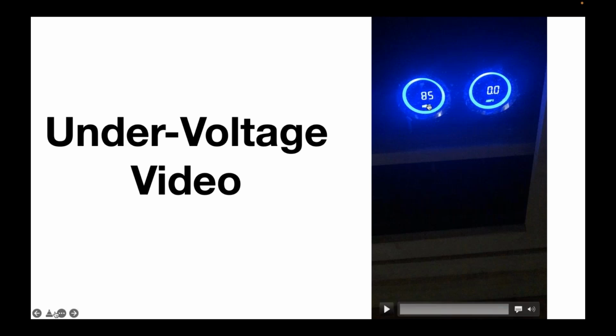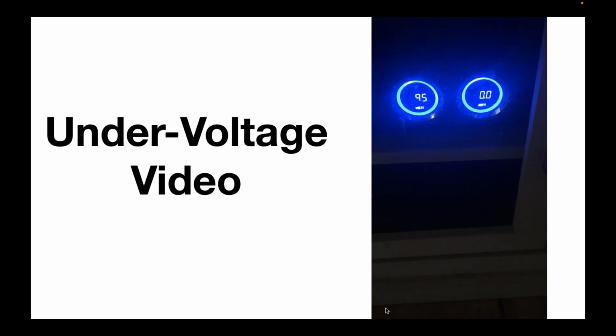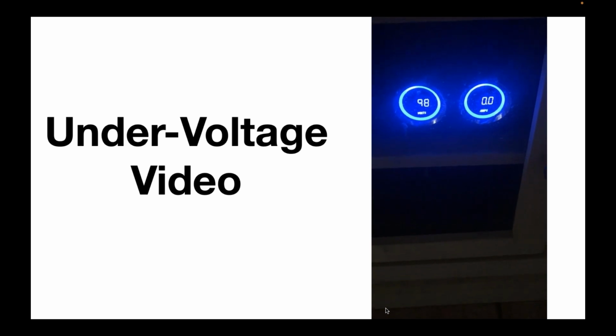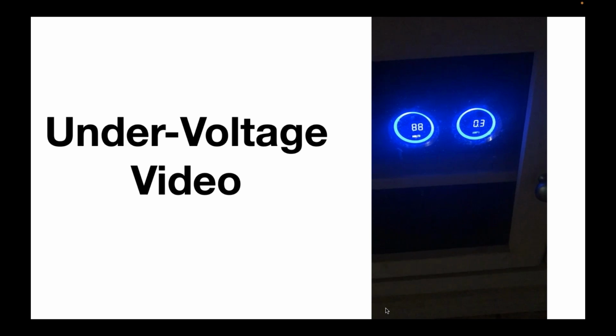When the voltage drops below about 85 volts, the unit automatically shuts off. As soon as it detects the voltage is back to regular levels, it turns back on. In this demo, the unit is connected to a voltage generator, a device that generates different voltages as a test. You can see the voltage dropping below 100 volts, and when it gets down to about 83 to 85, it shuts off. As soon as the voltage goes back over 100, it turns back on. It drops again, shuts off. That's how it works, based on detecting line voltage above or below a certain parameter.